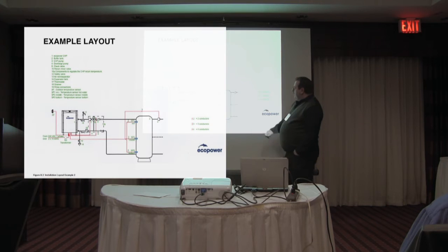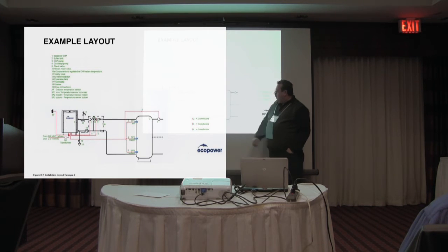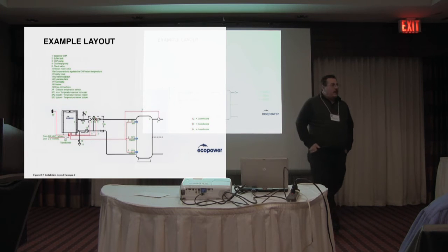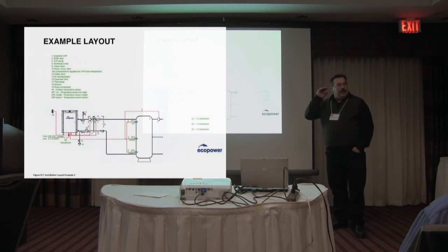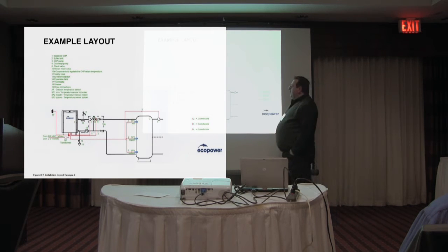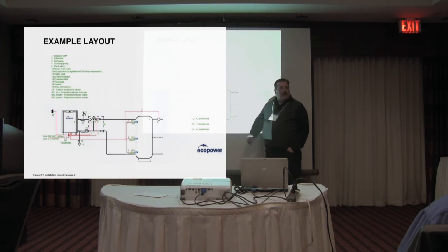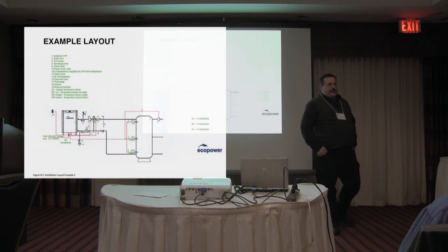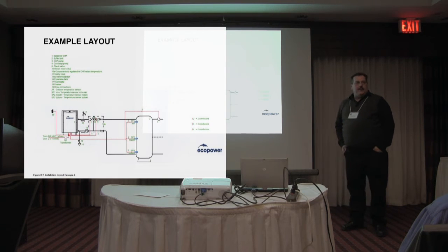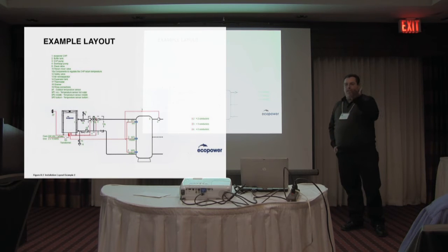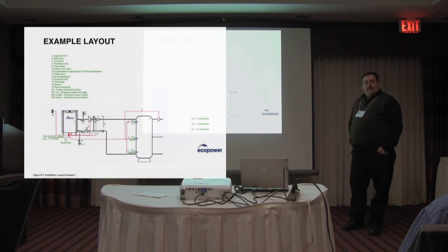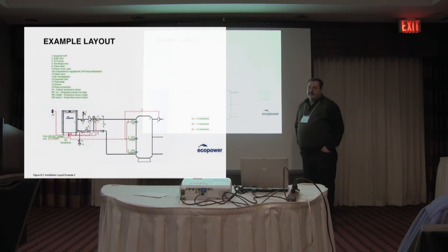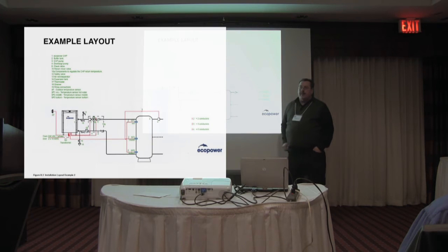So here they're showing 3 sensors in the tank, one at the top, one in the middle, one at the bottom. There's software and electronics in the unit itself where you can monitor and know exactly what's going on in that tank at any given time. One of the interesting things that you might see here is that the hot water is actually going into the top of the tank. I know with geothermal applications in the past, they always used to introduce the hot water at the bottom of the tank, allowing thermal migration within the tank. Here they're actually top loading the tank so that you always have the hottest water available for point of use. And it will stratify downwards. So at some point, these temperatures are all going to be close to being equal.